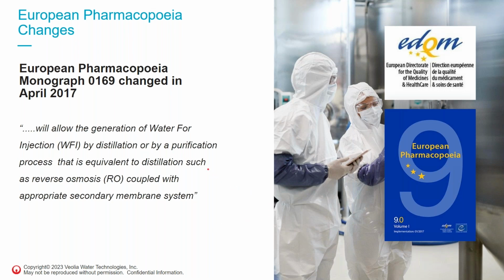But back in April 2017, the European Pharmacopoeia changed its monograph to allow membrane-based systems for WFI, and the definition came along with that: they will allow the generation of WFI water by distillation or by a purification process that is equivalent to distillation, such as RO, reverse osmosis, coupled with an appropriate secondary membrane system. They were looking at a twin-membrane system to do that.